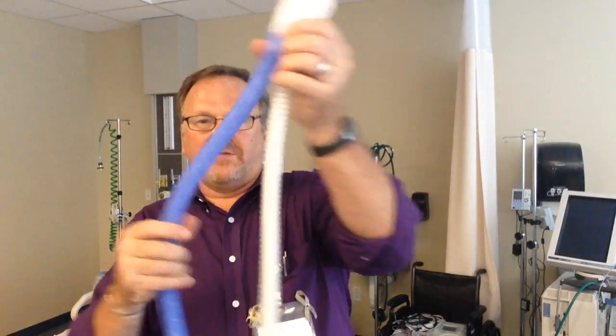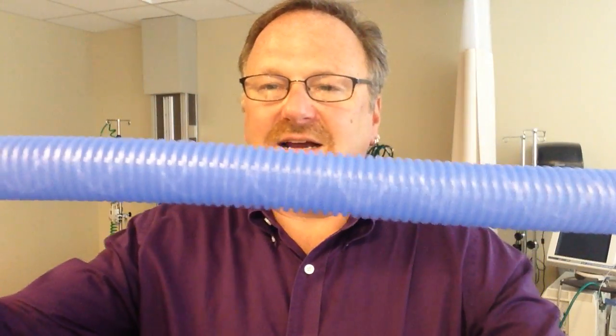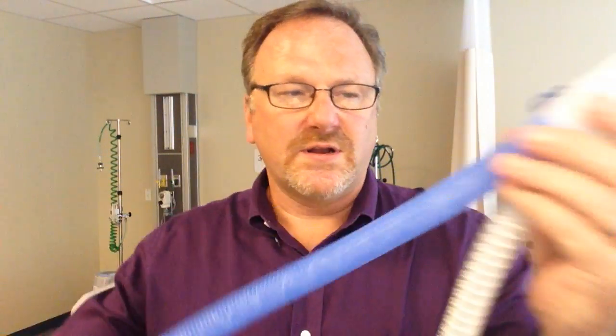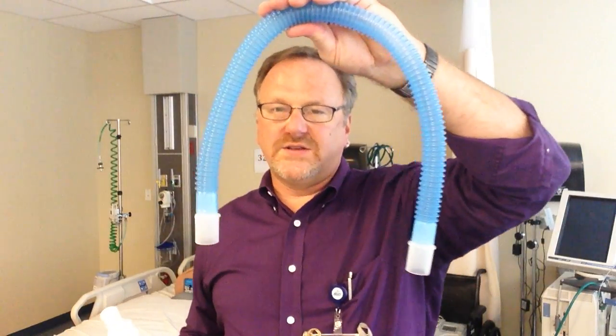What is the purpose of the wires inside the circuit? That is to assist in keeping the gas warm so all the humidity does not rain out. We want to deliver the patient 37-degree centigrade heated air, heated breath with 100% relative humidity. And my tube fell, but it also has a third piece to go from the ventilator to the heater chamber.